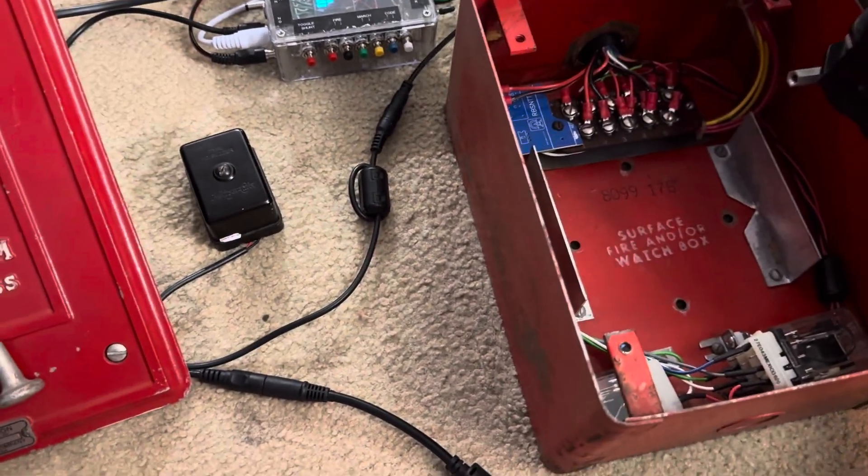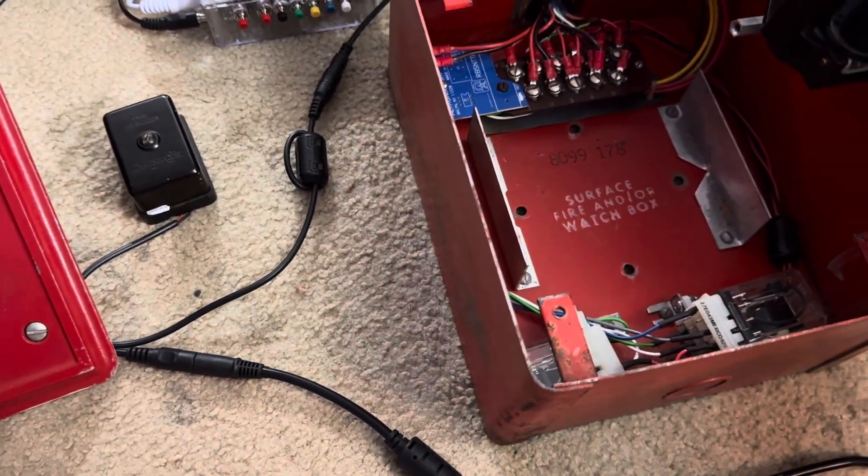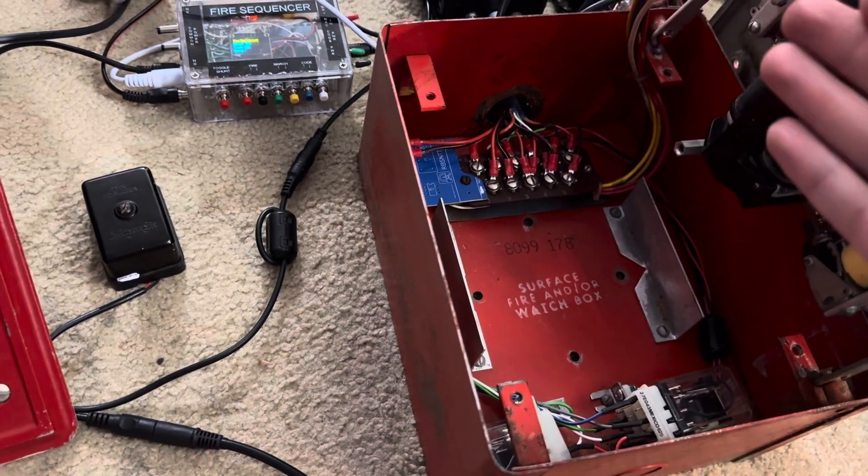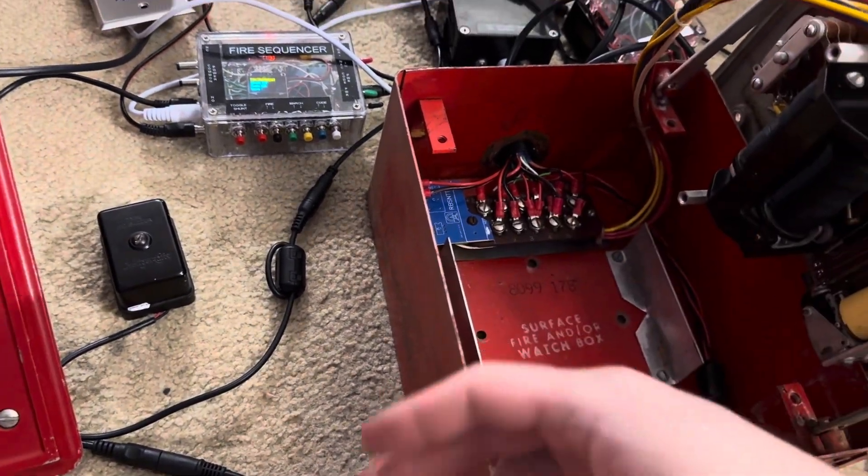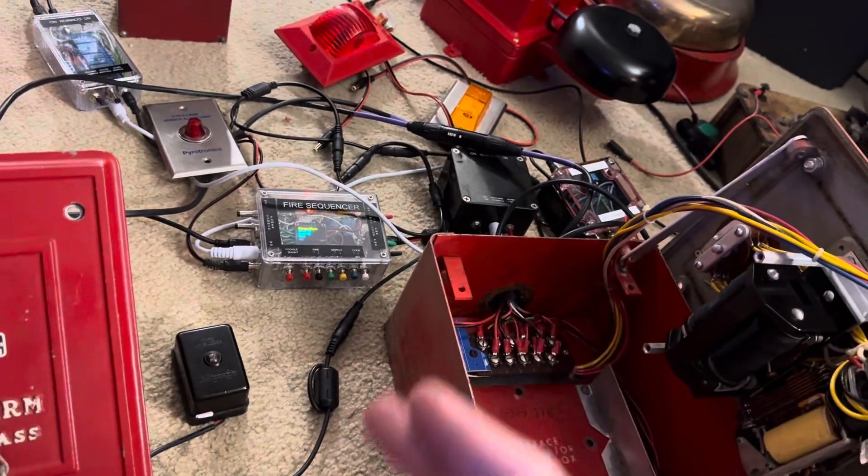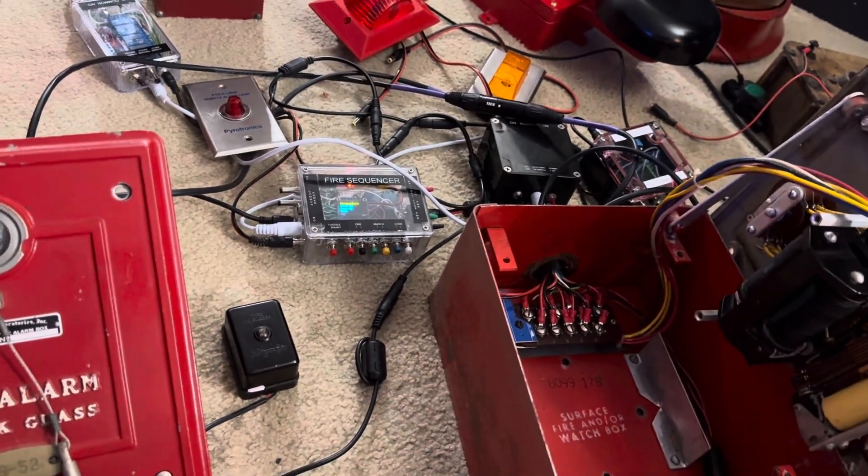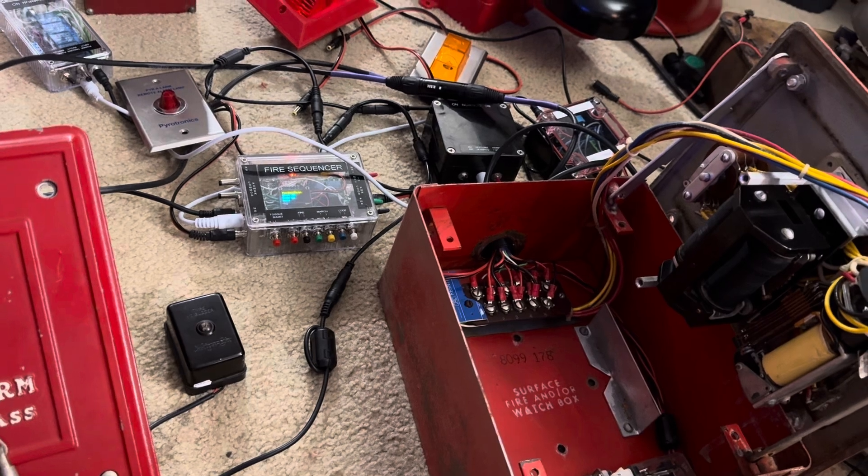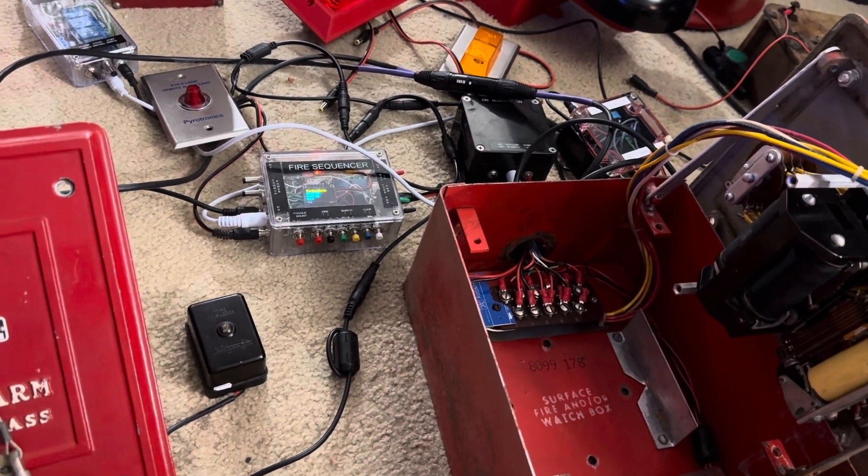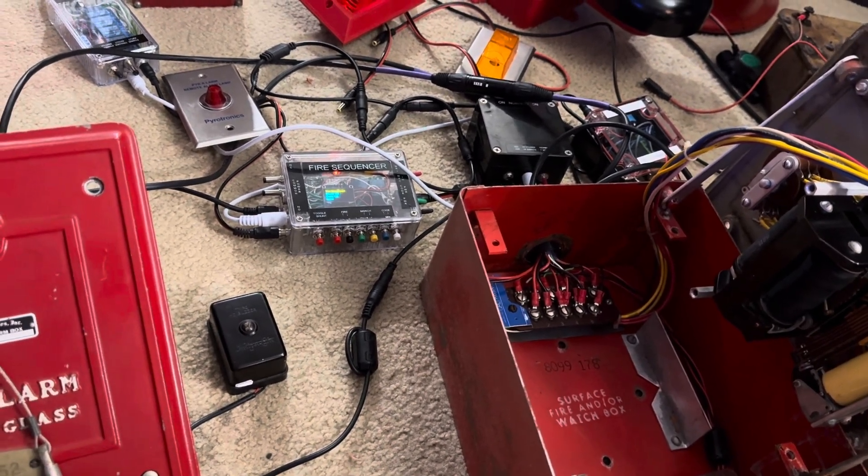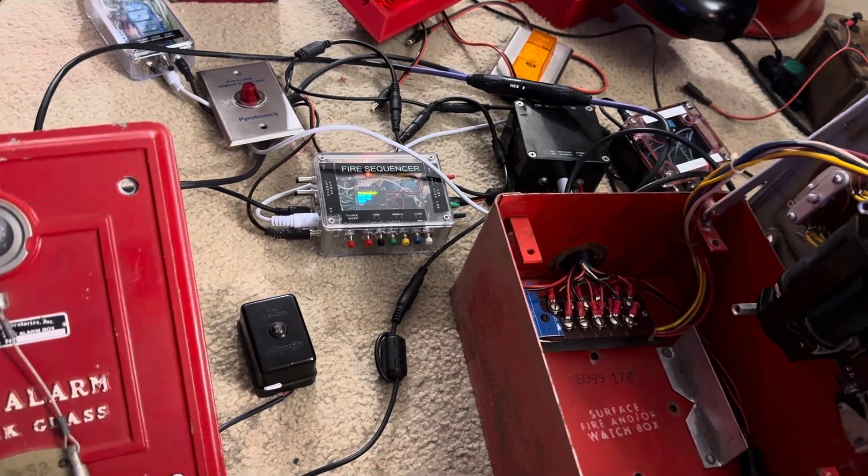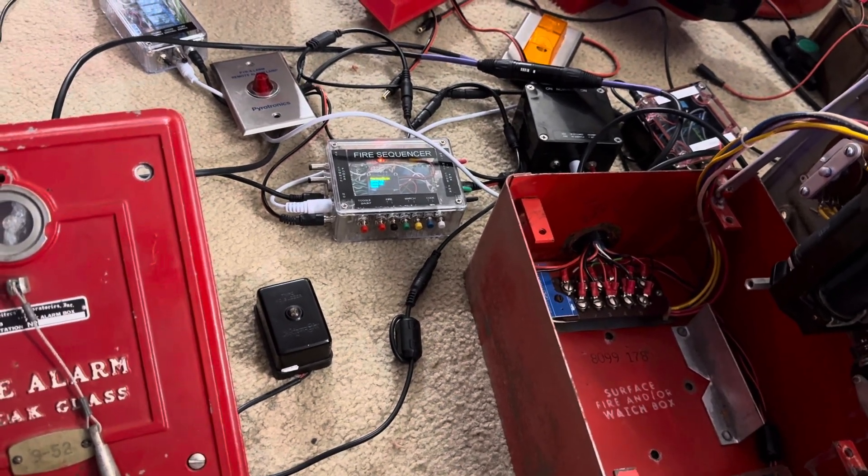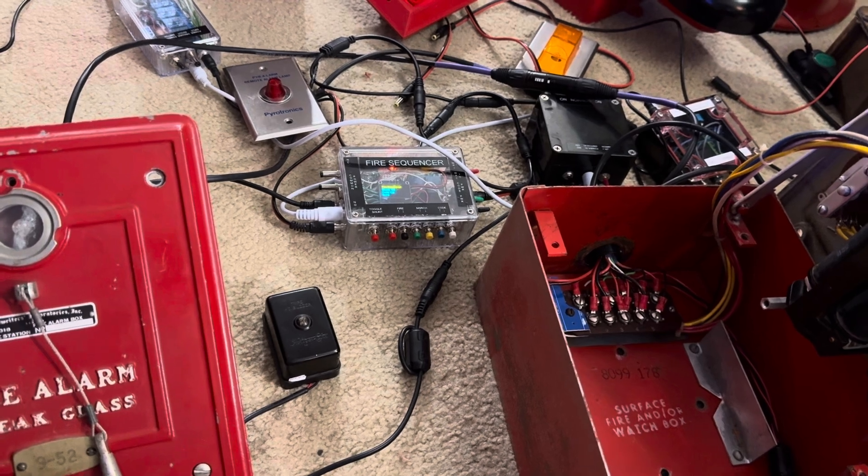But what I did learn is that on the original panel, the way you powered this thing is it's basically like a class A loop. You had in and out going to every station and both sides went back to the panel. Not entirely the most intuitive, but that's how it worked.